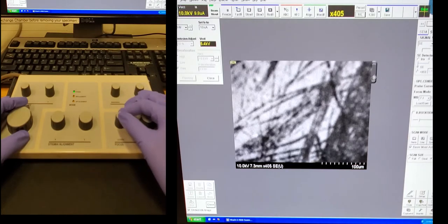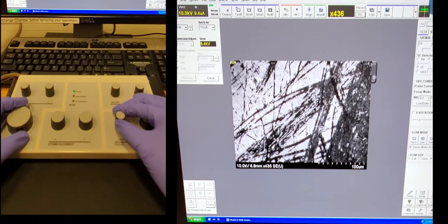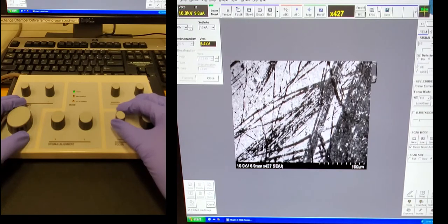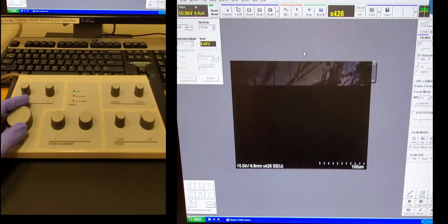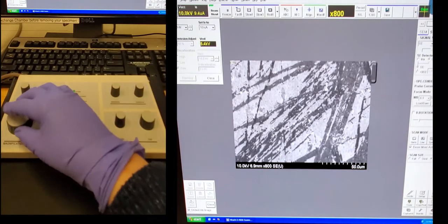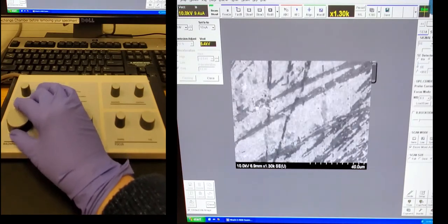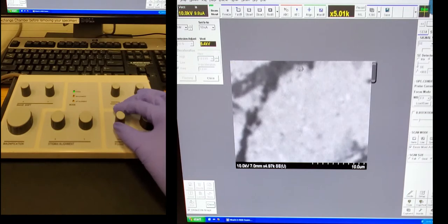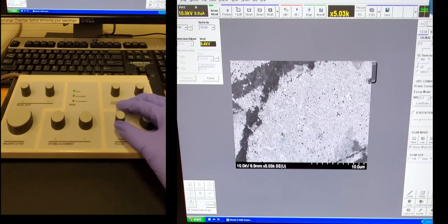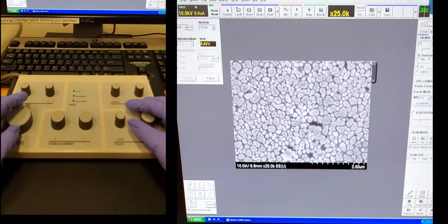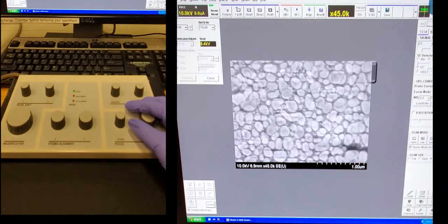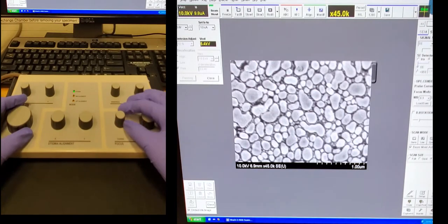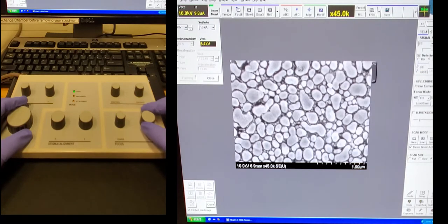You can see the image is shifting as I'm focusing. Hopefully after we do the alignment, we shouldn't have that problem. We'll adjust the color. You can do it manually as well. In this top right is the contrast. So these particles are quite small. We need to magnify in some more. So here is definitely at 45k. It's a good place to do the alignment, so we can just find a good spot.